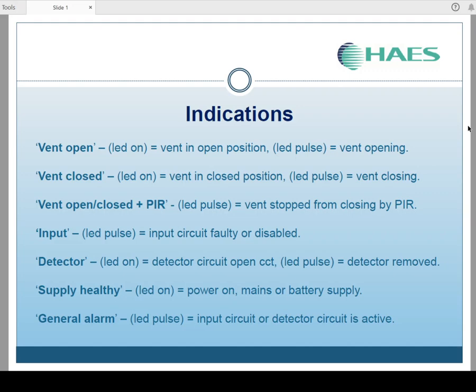You then have an input LED, again referring to the input circuit inside the panel. If the LED is pulsing, it indicates that the input circuit is faulty or disabled. Same for the detector circuit or the zone circuit. If the LED is on, the detector circuit is open circuit. If the LED pulses, the detector has been removed. The supply healthy LED, while it's on, it means power on, mains or battery supply. You then have your general alarm LED pulsing, which indicates the input circuit or detector circuit is active.